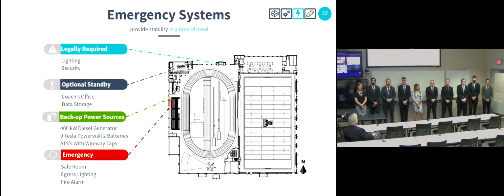Our emergency systems are fed from a 400 kilowatt diesel generator and 9 Tesla Powerwall batteries. The batteries are for in case the generator goes out. These batteries, the generator, and also our transfer switches are housed in the generator room in our safe room underneath the bleachers. This feeds our emergency system, which feeds the safe room, egress lighting, and fire alarm, our legally required system feeding more lighting and our security system, and our optional standby, which feeds our coach's office and our data storage.